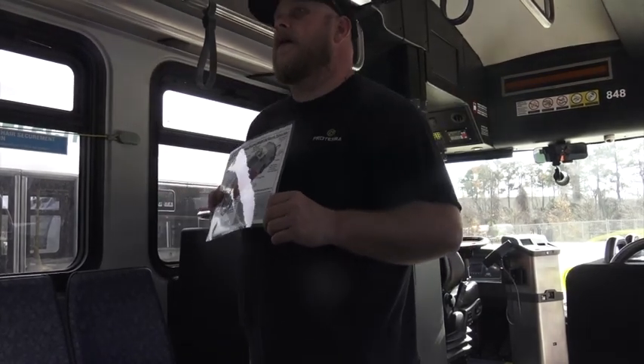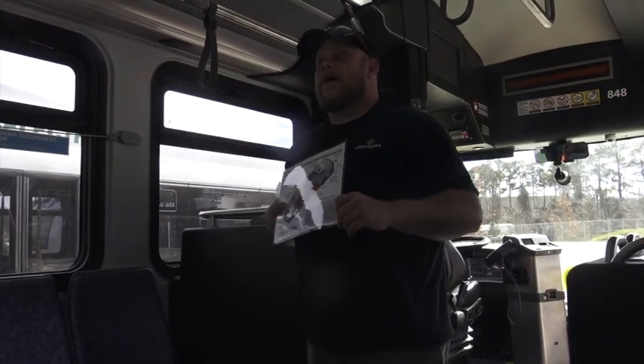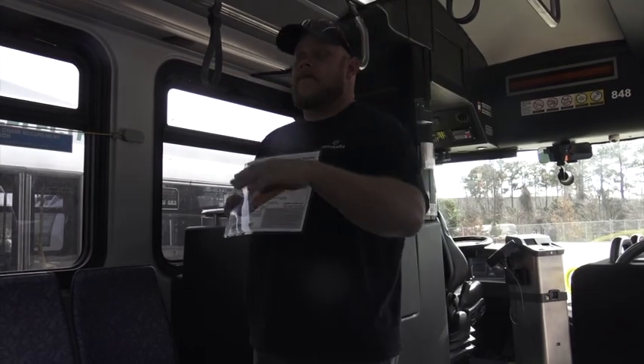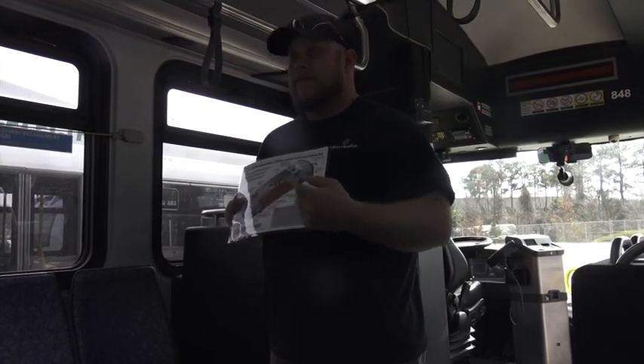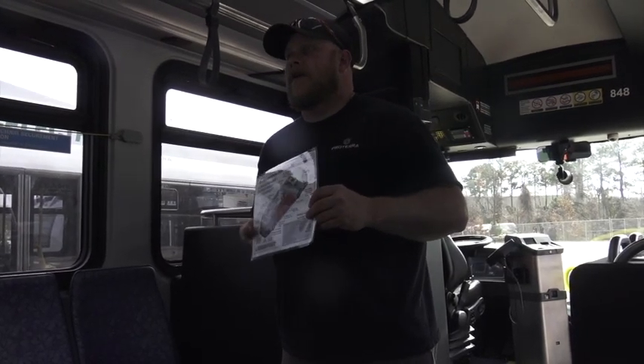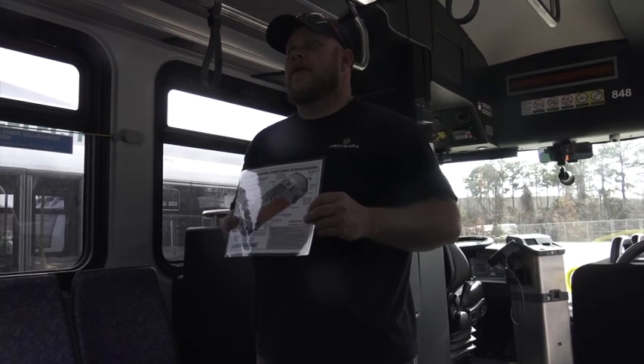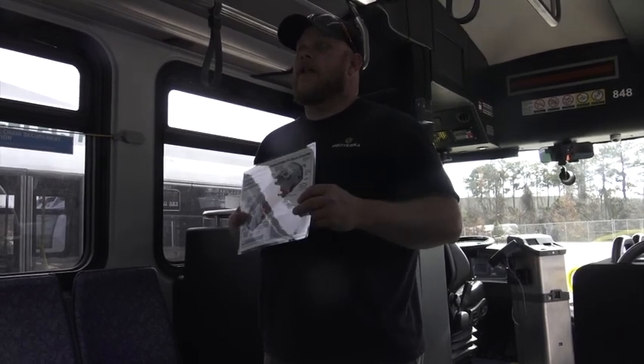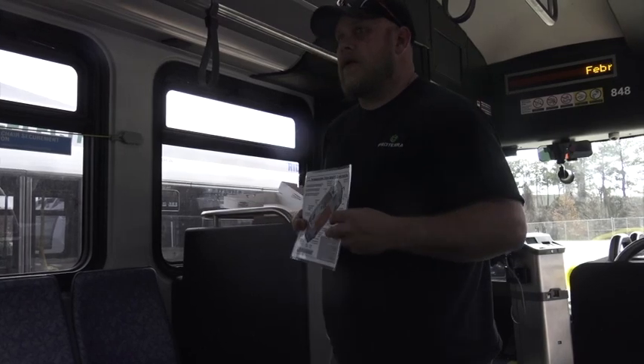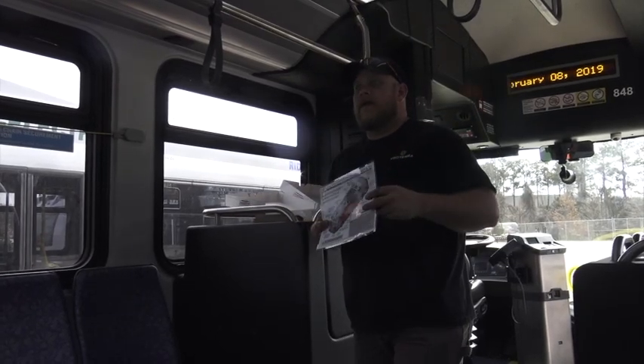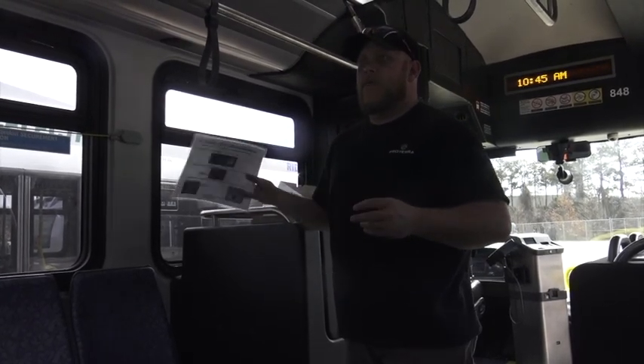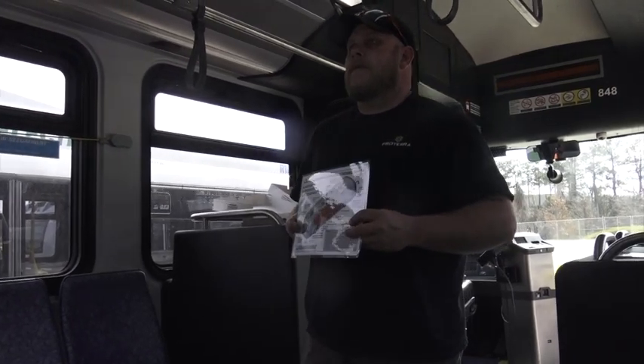It will not put this battery out. Each battery pack, there's 4 of them in the bus, as you can see in the big orange things. Each one holds 110 kilowatts of energy, or 110 kilowatt hours. So the incident energy in these packs is more than what a 480 transformer has coming off of it.